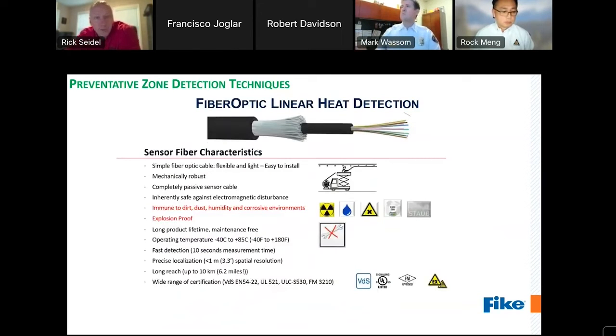Thank you. Another available preventative zone technique is linear heat detection, utilizing new and advanced technology with fiber optic cable. Conventional linear heat detection cable relies on a given length of wire to melt at a determined temperature to signal that a thermal event is occurring. Fiber optic linear heat detection is a programmable and addressable linear heat detection system that can continuously monitor and measure the temperature along the entire length of the cable, up to 6 miles, and allows for different set points to be programmed in varying and/or overlapping lengths of the cable. Fiber optic cable is extremely light and flexible and completely passive with no power or voltage traveling through it, which makes it a very effective solution in very challenging or rated environments.